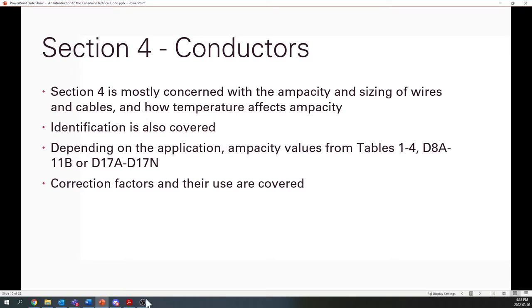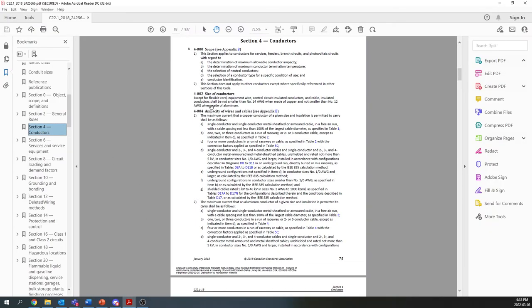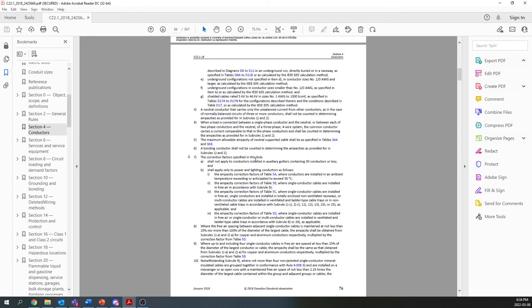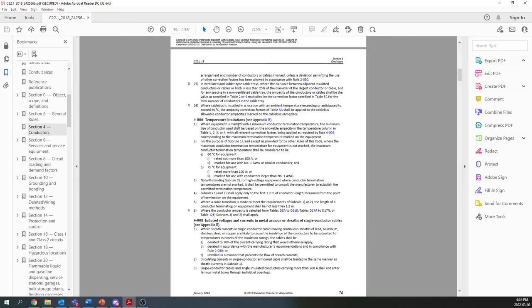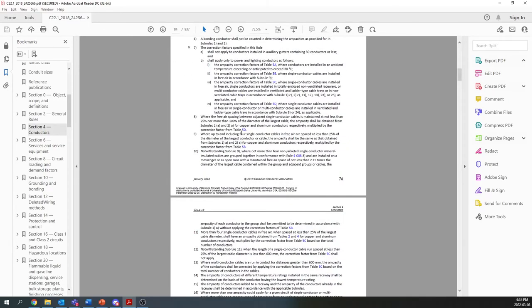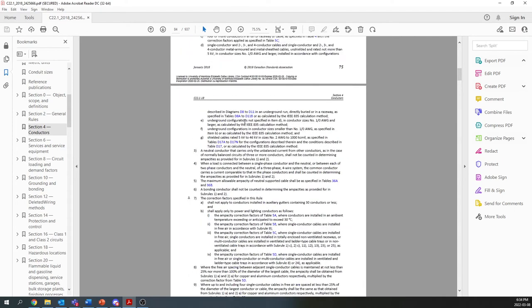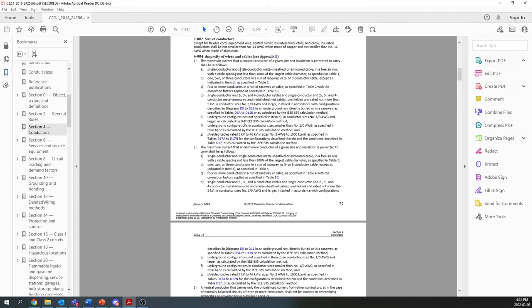Yeah, so that's conductors. If we go to section four here, we'll see rule 4-004 is definitely one of the most important rules in the whole book. It is like 3 pages long, and it covers all kinds of different wires, cables, and different installation configurations, and how you might calculate the ampacity in those different configurations, and even for different sizes as well. So copper and aluminum, of course, are really the only two materials used for commercial industrial wiring.